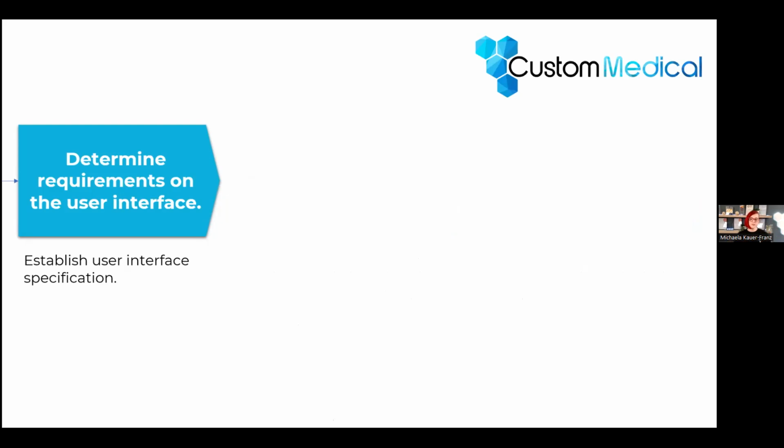After you've done all this, you're thinking about the requirements on the user interface. So basically, now you know what is risky. Now you know potential hazards and harms, and you know your user group. So you start to think about how you can do a proper risk mitigation. What kind of requirements do I have for my user interface to make sure that we are serving the right user group, that we're fulfilling the right purpose without posing any additional risk? And we're now in step 6.